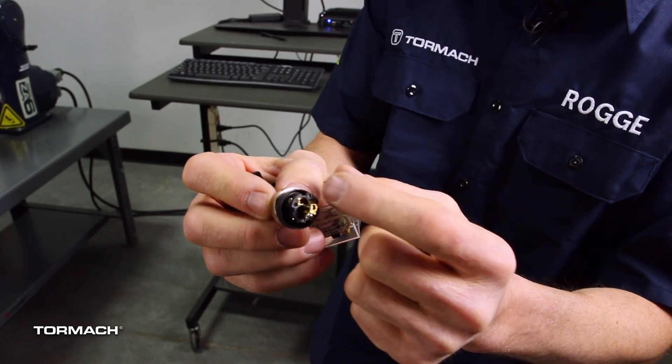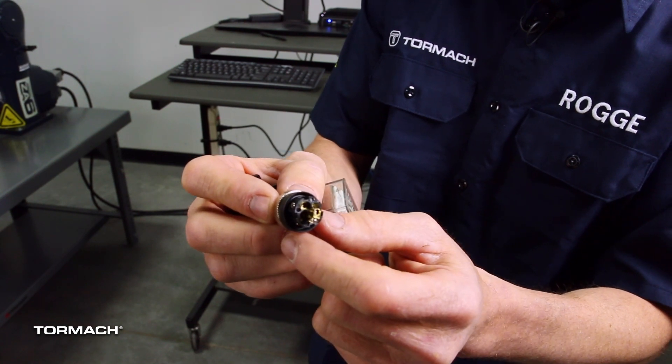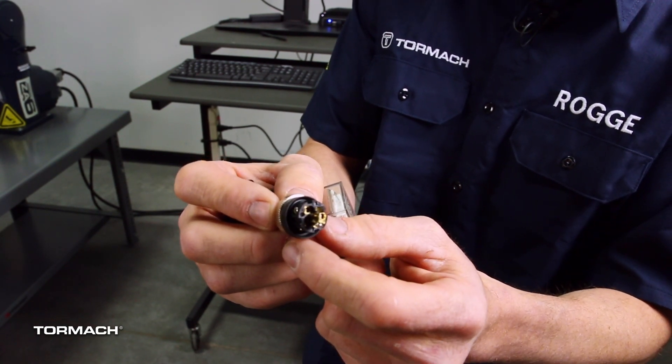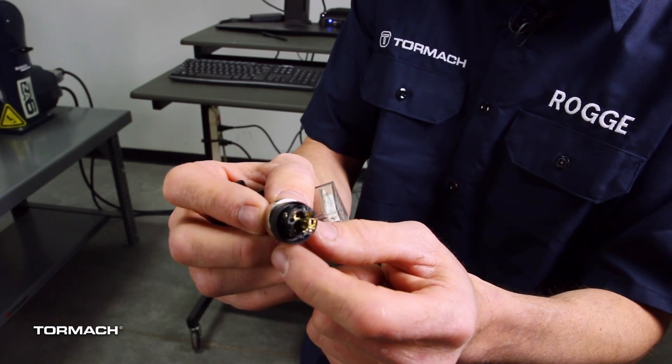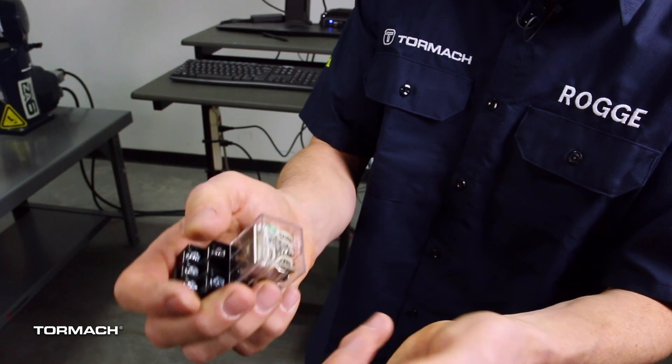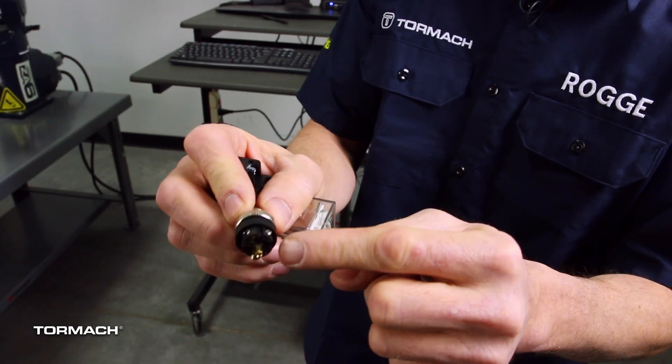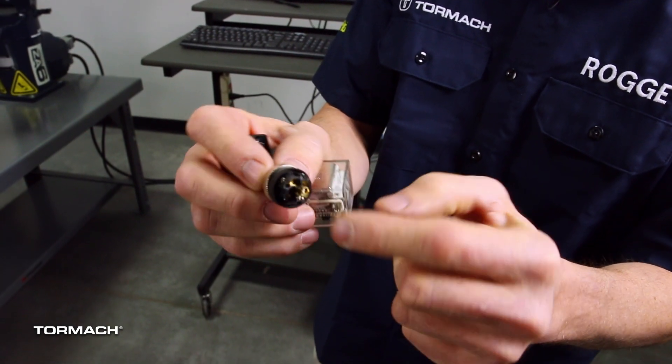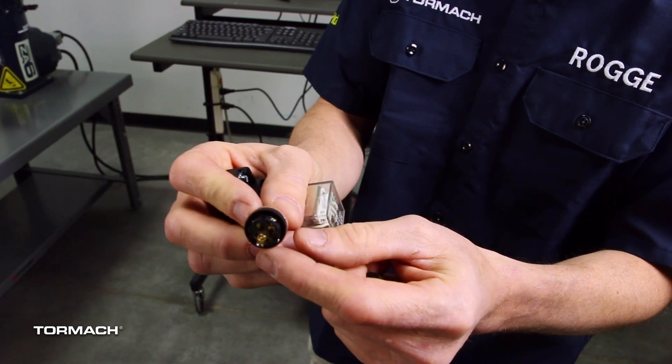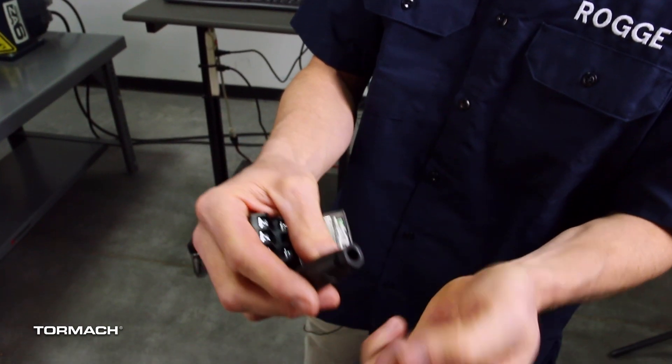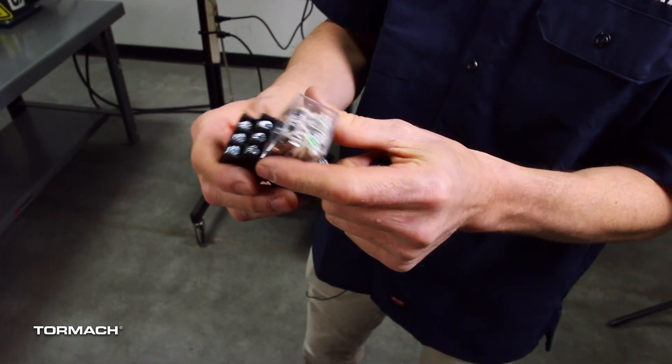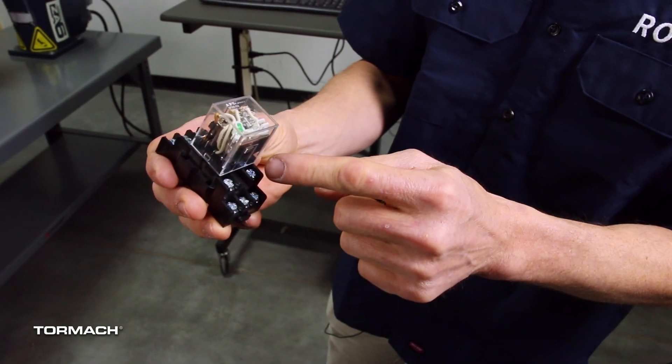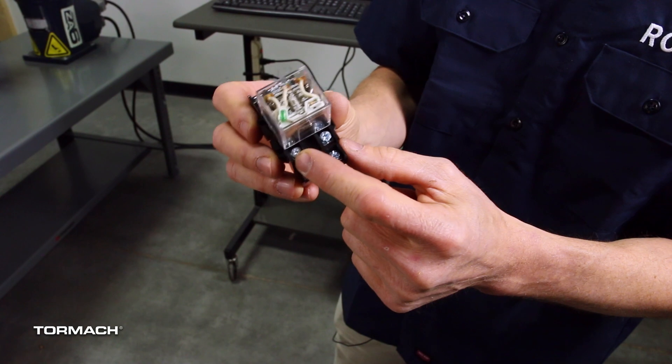We're going to find which two pins are responsible for the 24-volt switched output, we'll do that by looking in the manual for the ZA6, show you how to read the manual and the schematic. Then we're going to, just using these screw terminals, connect our negative and positives to the switched output. We'll go ahead and route them through the little strain relief here on the back. And we'll take those over and connect them to the coil terminals on this contactor.